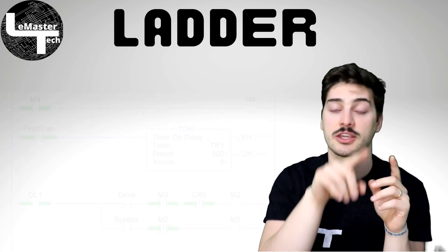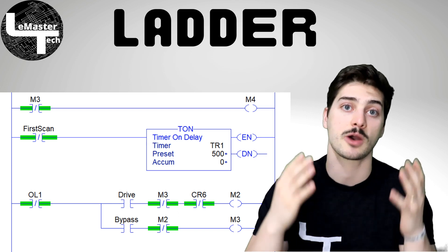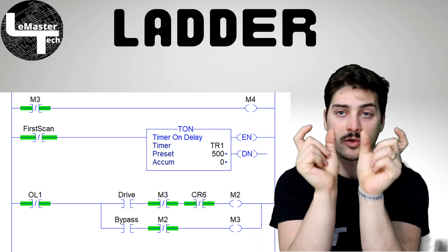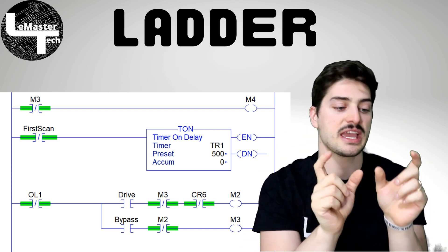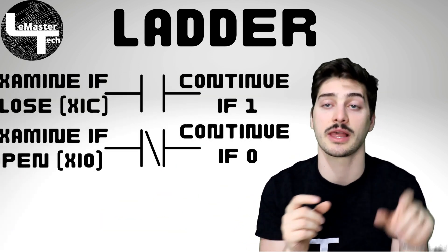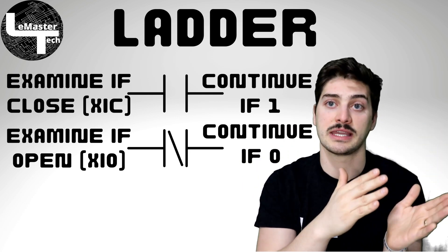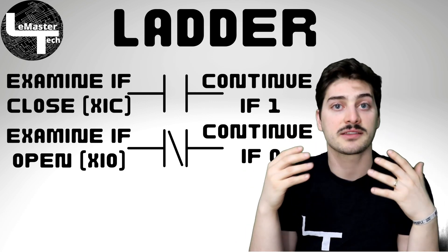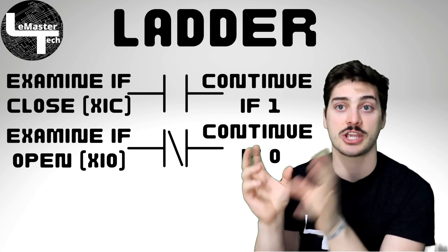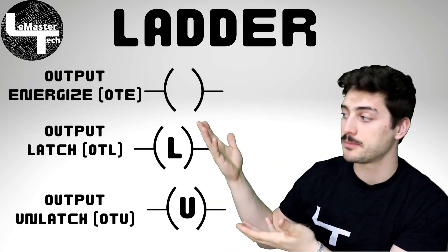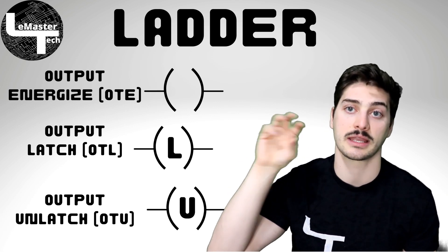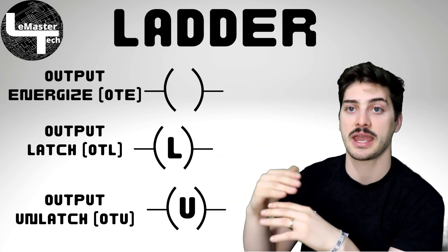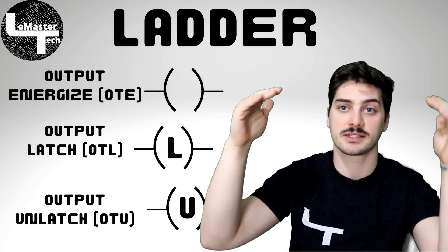In Ladder Logic you can almost trace a flow of electricity through your program, which is why it looks like a ladder — rung after rung. The individual modules come from the relay concept. The two most common instructions are Examine If Closed and Examine If Open, which are basically an IF and an IF NOT — checking if a condition is a one or a zero. To set boolean outputs, you need to know the OTE (energized the whole time the rung is true) versus the OTL and OTU pair, which latch and unlatch a binary condition.